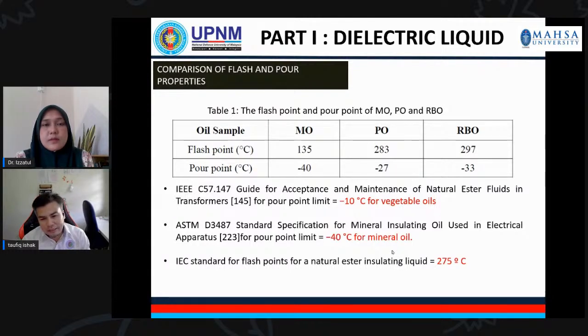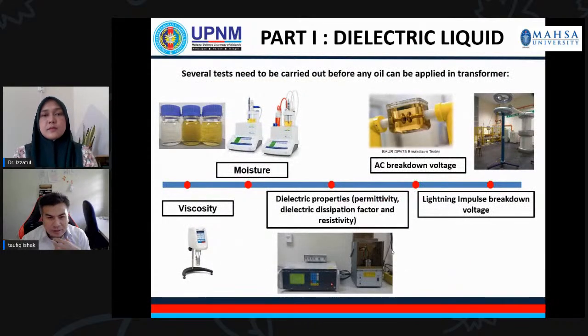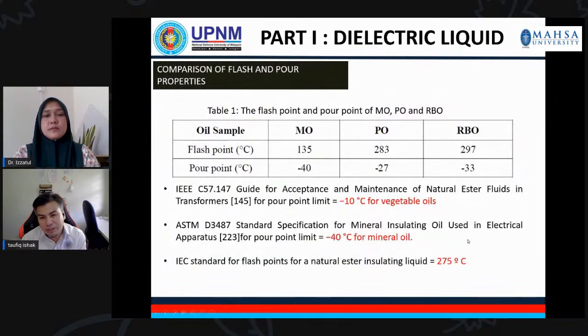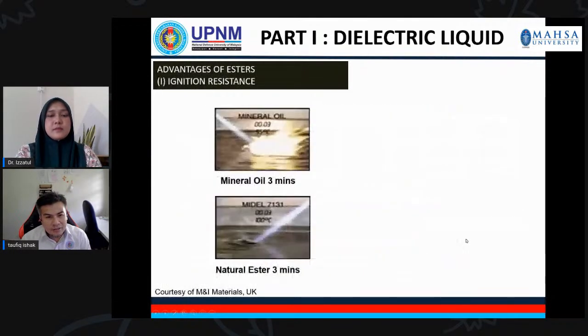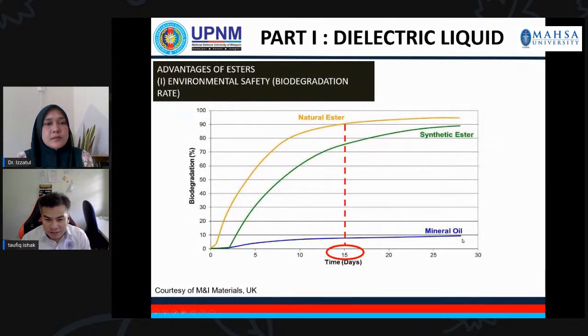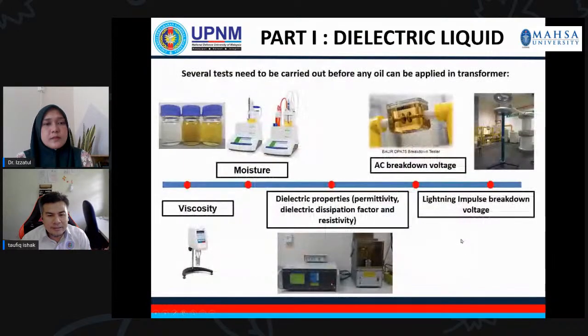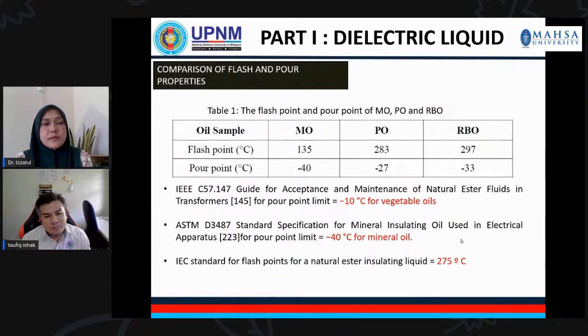So when we look at the three important criteria from the results that we saw before, the vegetable oil has actually surpassed all the minimum requirements to be a transformer liquid. First, very good fire resistance. Second, in terms of biodegradation. And the last one is in terms of flash point and pour point. So the main three criteria are already passed by all these vegetable oils.